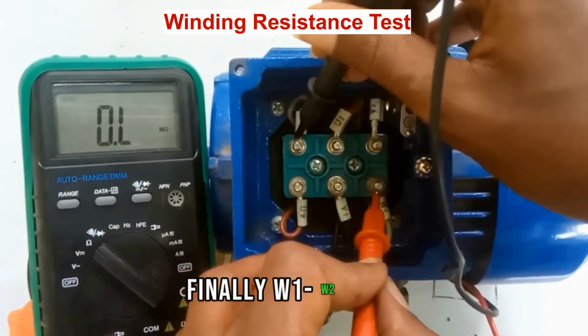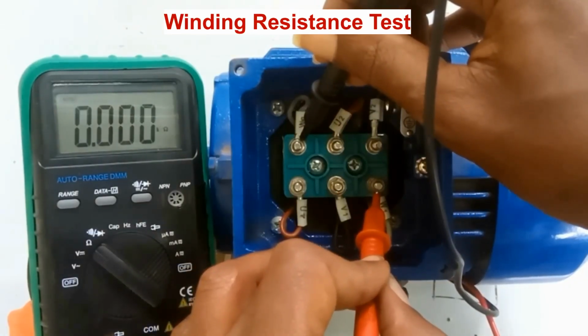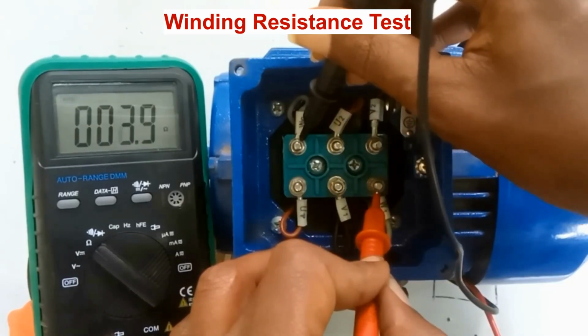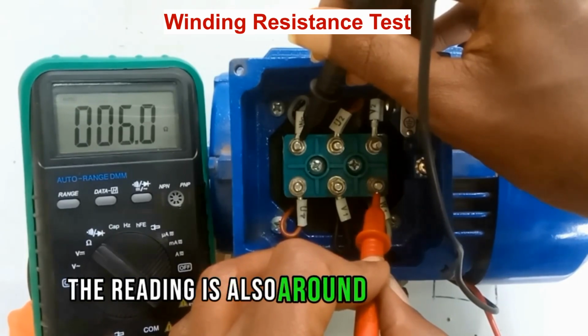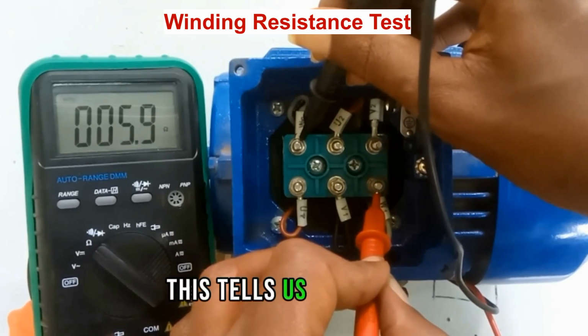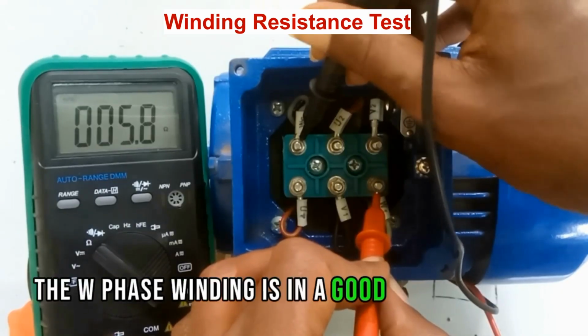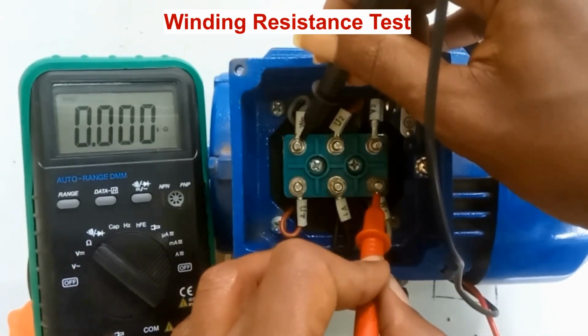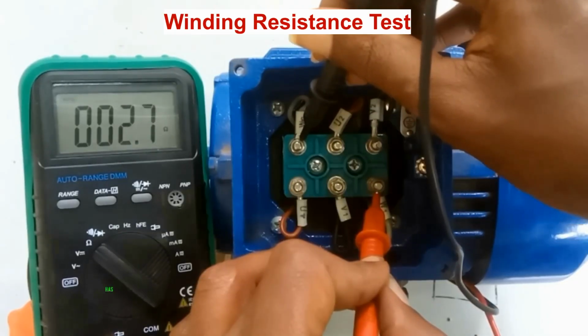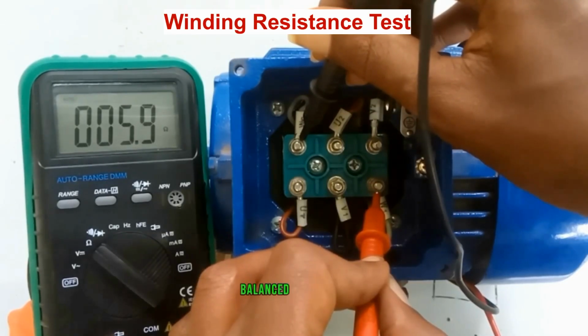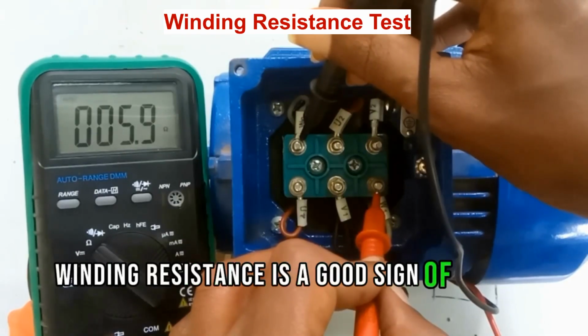Finally, W1 to W2. The reading is also around 5.9 ohms. This tells us that the W phase winding is in good condition. Notice that all 3 windings have nearly the same resistance. Balanced winding resistance is a good sign of a healthy motor.